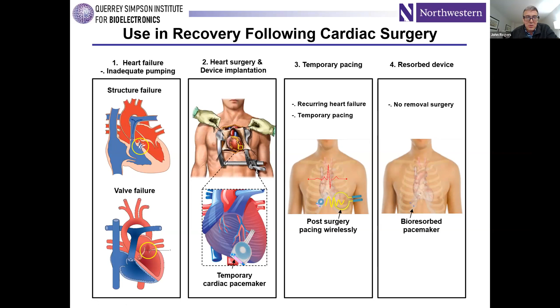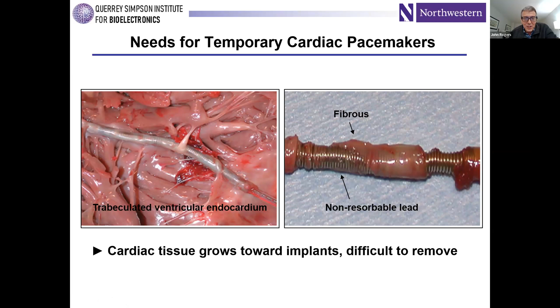So this makes sense if that surgical extraction process is costly or it exposes the patient to additional risk. And it turns out that there are significant risks associated with that removal. The problem is that these pacing leads typically become encapsulated in fibrotic tissue during that recovery period. So when they need to be removed, they're simply pulled out of the body. It's a transcutaneous interface to an external power supply to provide the stimulating pulses for doing the pacing. You pull it out of the body, that fibrotic tissue rips, and in certain instances, the tearing of that fibrous tissue can lead to damage to the healthy underlying cardiac tissue, thereby creating internal bleeding that can be a very high risk factor for the patients.